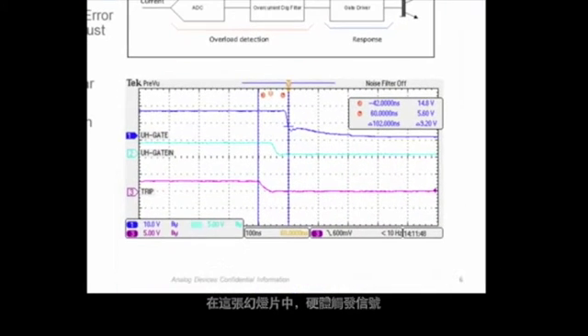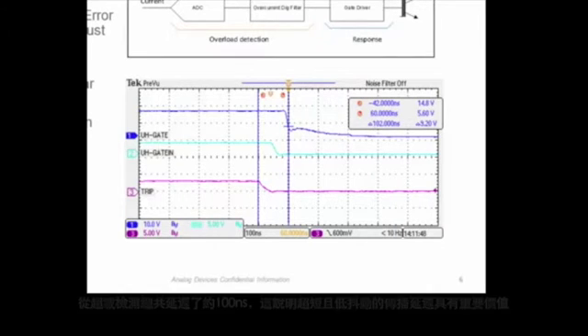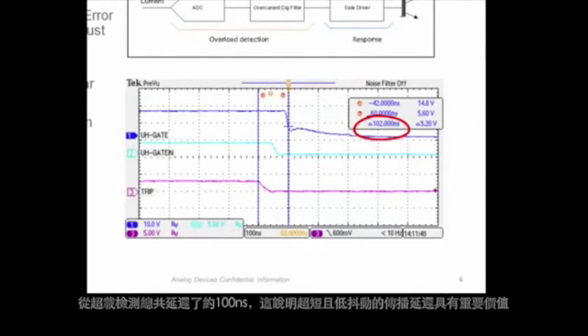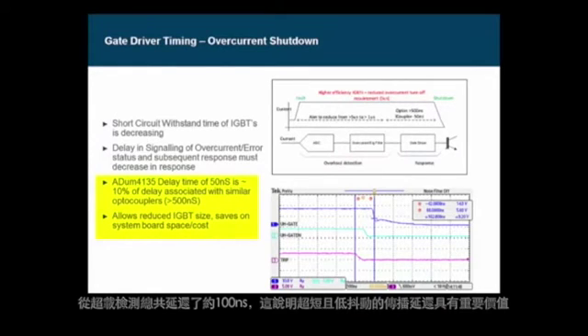In this slide, the delay between the hardware trip signal, the PWM output signal, and the actual gate emitter waveform of the upper IGBT in one of the inverter legs is shown. The total delay to commencement of IGBT turn off is seen to be about 100 ns from detection of the overload, showing the value in having such a short and low jitter propagation delay.